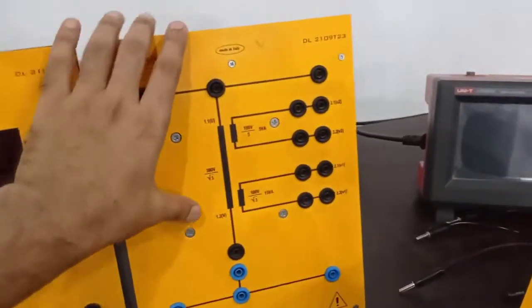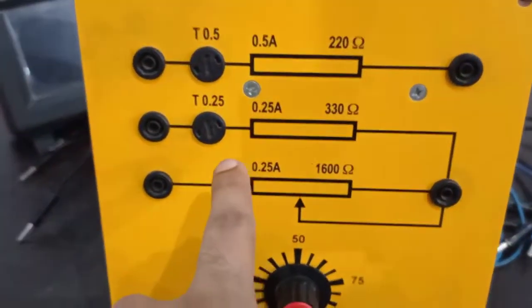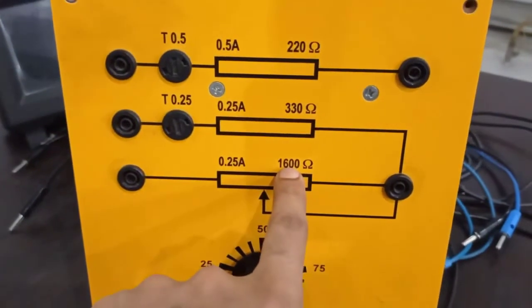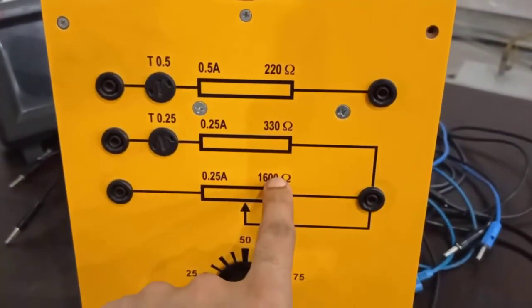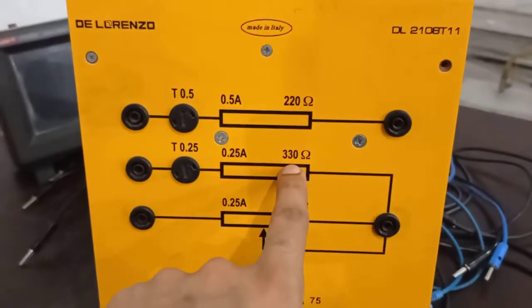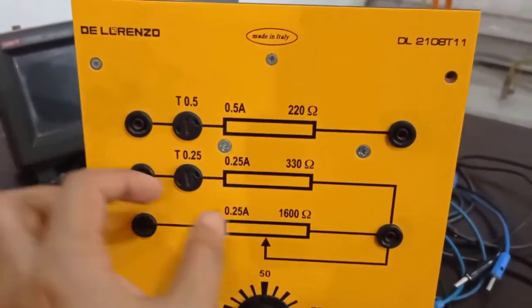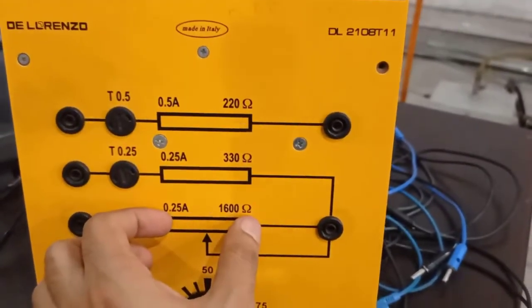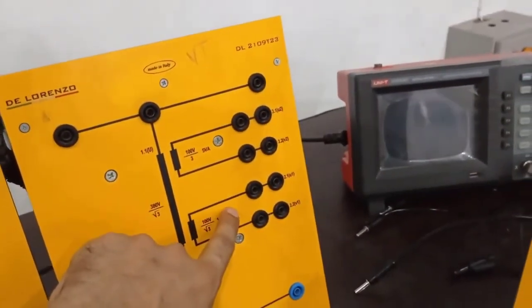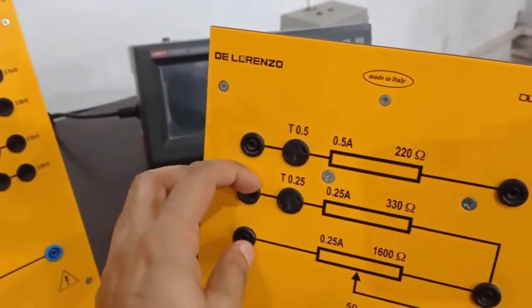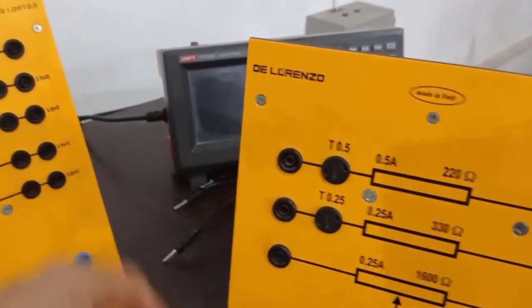Now for this voltage transformer, the secondary side burden is given over here. The difference between the burden of the CT and the burden of the VT is the value of impedance. Here the impedance value is 1600 ohm, which can vary from 0 to 1600 in series with 330 ohm. So use these two terminals to make sure that 330 is in series with 1600 ohm. That would be connected across the secondary of this voltage transformer. You will also observe the waveform of voltage by connecting the digital storage oscilloscope across the secondary of the voltage transformer as well.